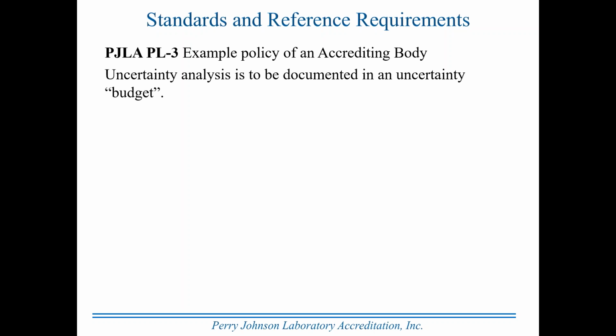Uncertainty analysis is to be documented in an uncertainty budget. Nowhere in the standard does it require you to have an uncertainty budget, but at PJLA, you have to document the information somehow, and rather than just writing it on the back of a cocktail napkin, Perry Johnson said you need to develop an uncertainty budget. How you do that is very, very open to your preference. Typically, it's a matrix with information entered in horizontal rows. Could very easily be a matrix with information entered in vertical rows if you choose. There's a number of good examples on the internet. Perry Johnson has some good examples on their website. So look those things over and decide on a format you want to use and be consistent, because it really gets confusing if you do multiple types of calibrations or tests and you have multiple presentations of how you do measurement uncertainty analysis.